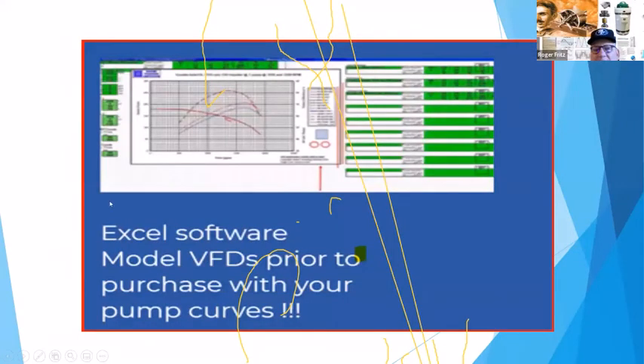This piece of software is available from a guy that I know down in Australia who actually designed software that you can load in. Where are you going to be running the speed points of the VFD? And then it automatically calculates where that optimal percentage is, because these curves all change based on speed and impeller size and RPM.